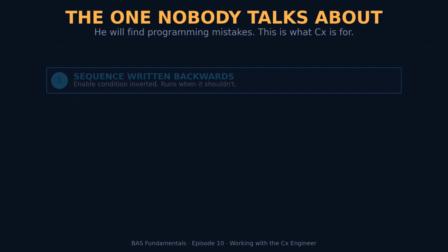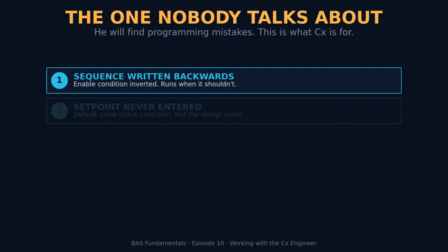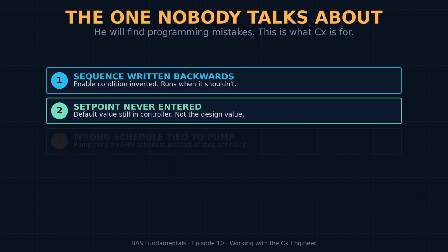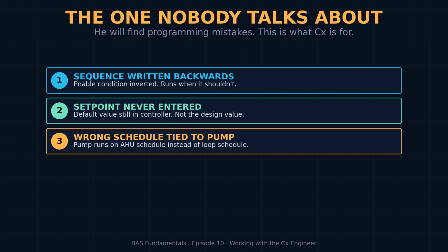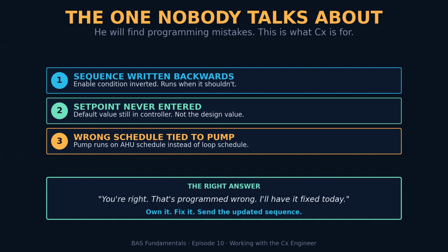Here's one nobody talks about. The CX agent is going to find things the programmer did wrong. Sequences written backwards, set points that never got entered, a pump enable written to the wrong schedule. That is not an attack on you. That is exactly what commissioning is for. When he finds one, the right answer is, you're right. That's programmed wrong. I'll have it fixed today, and here's the updated sequence when it's back. Own it. The controls techs who argue about programming errors during commissioning are the ones who have to come back 6 months later anyway.